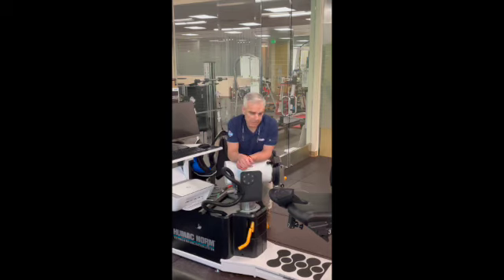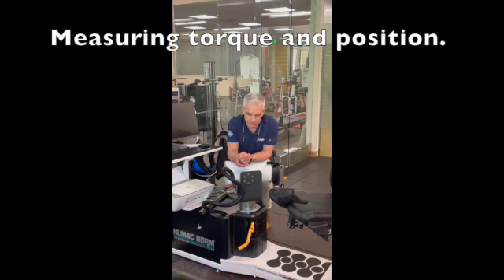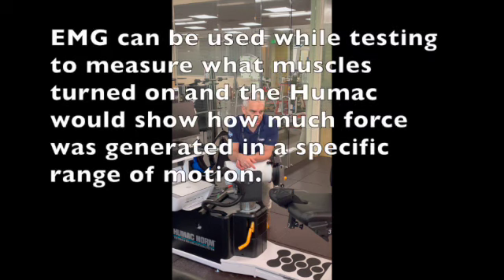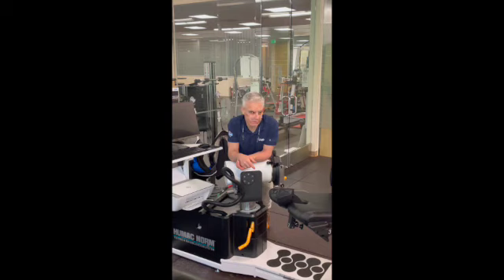In regards to the data, we're really measuring two things: force — how much the patient puts out, which we call torque because it's rotary — and position, meaning where the person is in the range of motion when we're measuring the force. You can stream the data out the side as an analog output and connect it to something else, like an EMG system. The EMG tells you when the muscle turns on; our machine tells you how much force it generated and where the joint was when force was generated. That's how you use the two together.